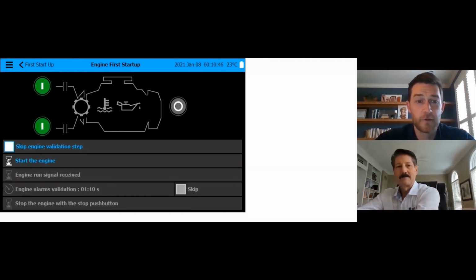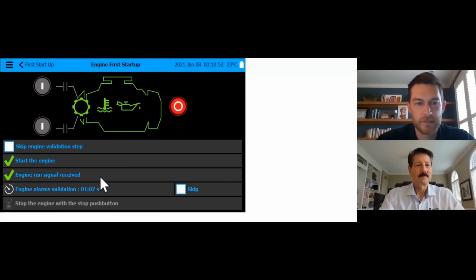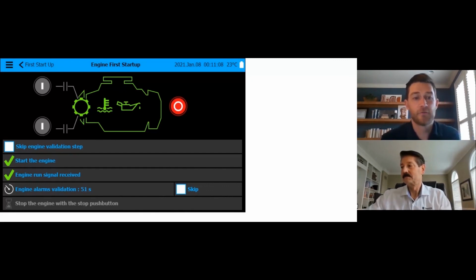So from here, we're going to want to manually crank it. It's going to have to go through checking all of the continuity of the wires that are connected from the engine to the control panel. So that's what it's going to be doing for the next 1 minute and 2 seconds: engine alarm validation. You can skip that, but it's best to let it go ahead and do that. That way you can verify that everything has been connected properly. For the demo, there is actually nothing connected, so we could skip this one if you wanted to.